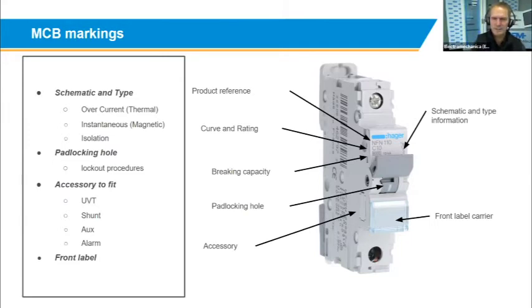Just on that, keep in mind that a circuit breaker is installed in an installation not to protect your equipment, but to protect the installation. So normally it's there to protect your cables and stuff like that. If you want to go deeper and you would like to protect an electric motor, the best thing to do is to add a contactor with an overload to get the settings closer to protect the motor, because the circuit breaker will only protect it on short circuit. But for overcurrent, obviously, an overload would be a lot better.